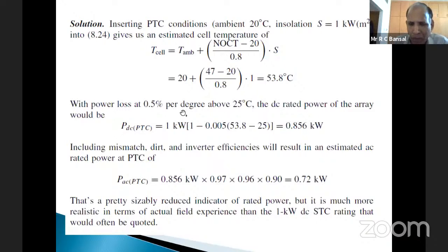So you will see that because of this higher temperature, the DC power output from the PV module, okay, its power rating was 1 kilowatt. Okay, but because of the different cell temperature of the module, what we actually get, that there is power loss of 0.5% per degree above 25. So the actual cell temperature is 53. So because of that, the DC power what we will be getting from the PV module is 856 watt.